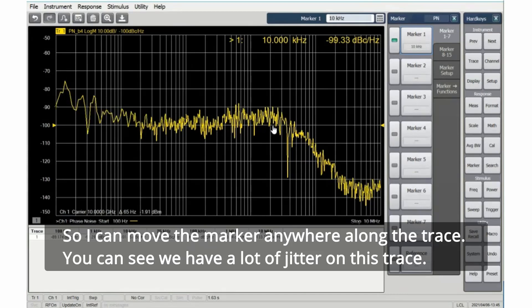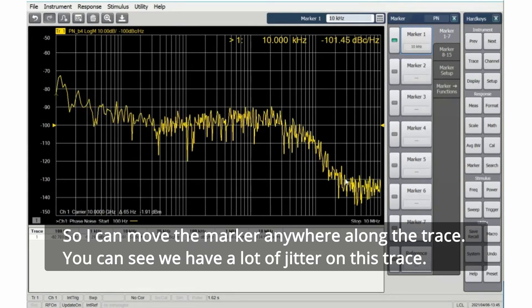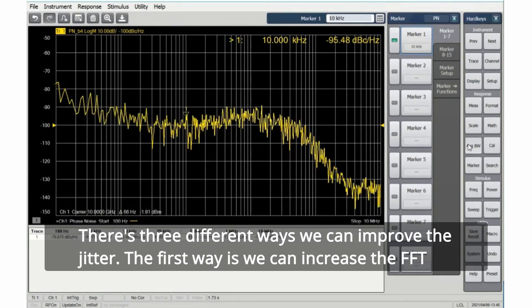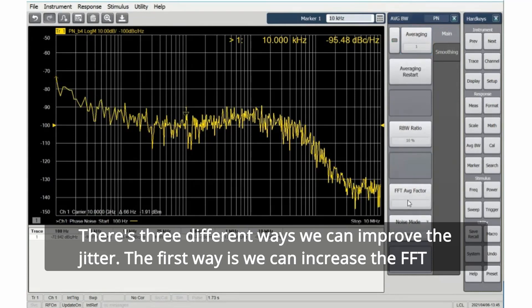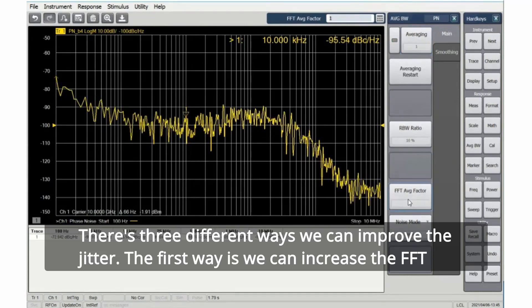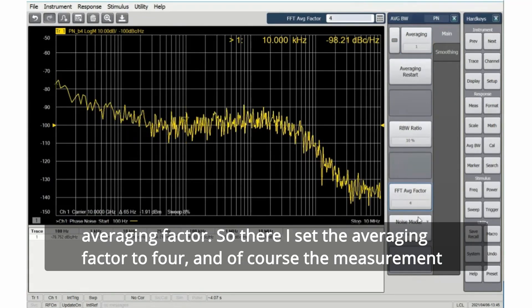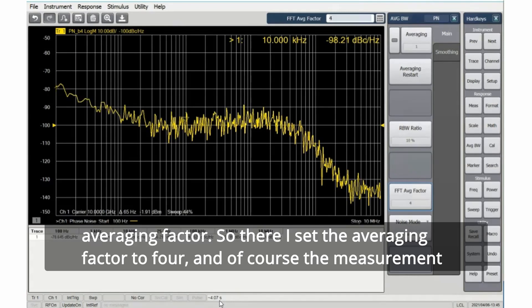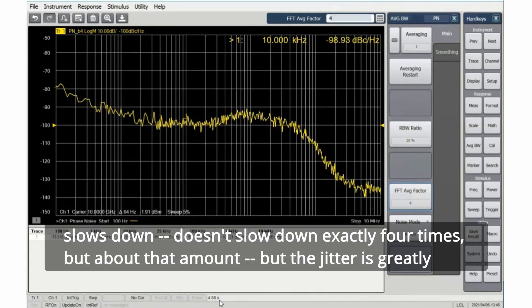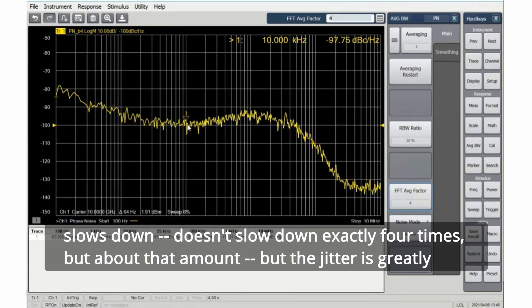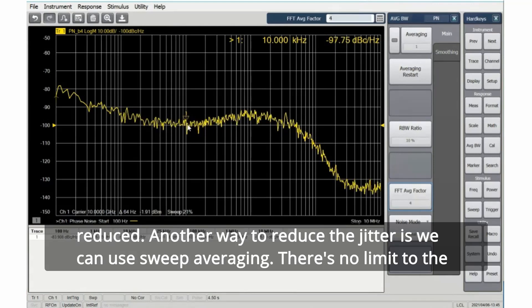So I can move the marker anywhere along the trace. You can see we have a lot of jitter on this trace. There's three different ways we can improve the jitter. The first way is we can increase the FFT averaging factor. So there I set the averaging factor to four. And of course, the measurement slows down. It doesn't slow down exactly four times, but about that amount. But the jitter is greatly reduced.